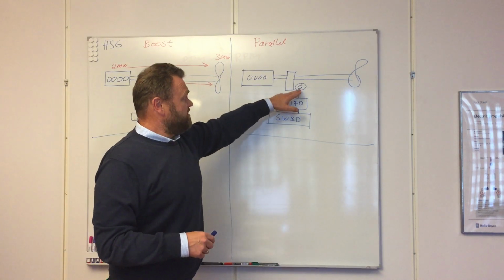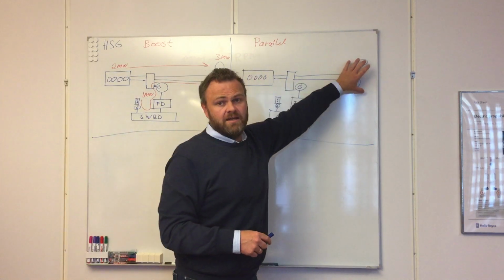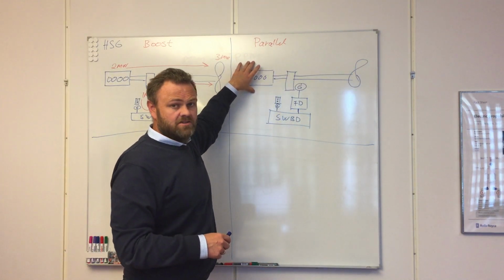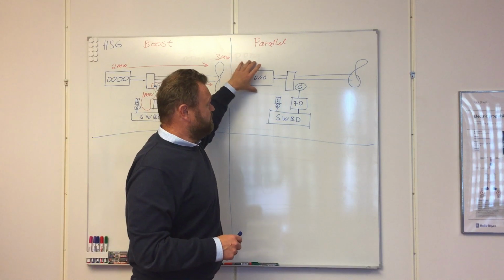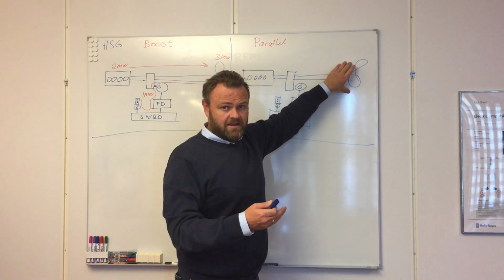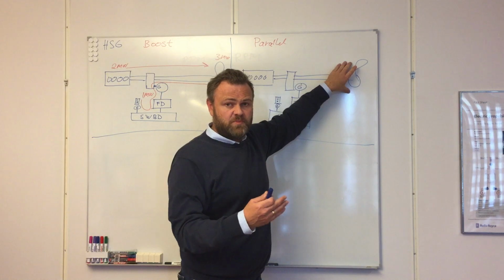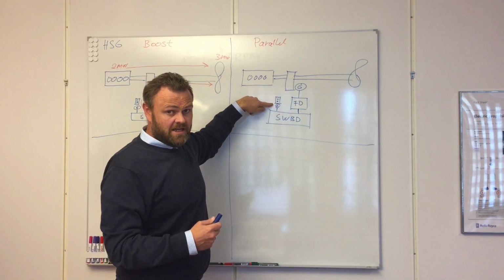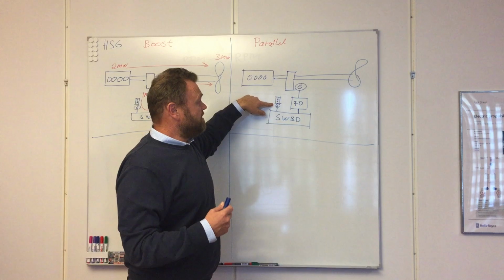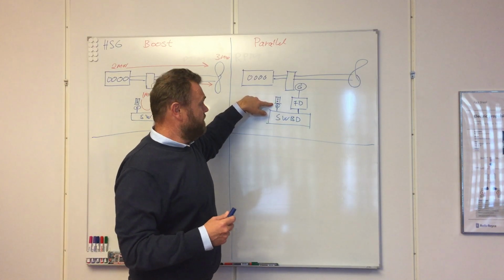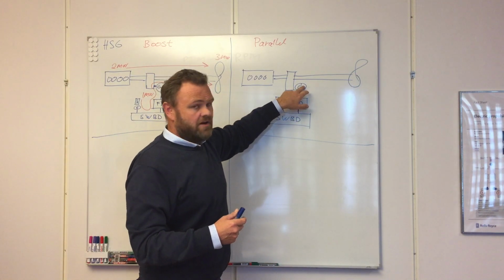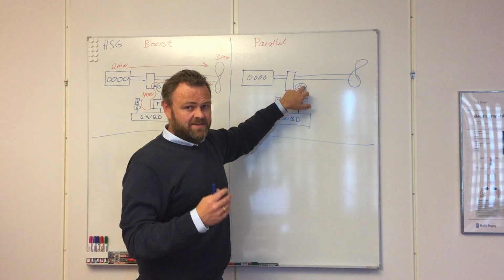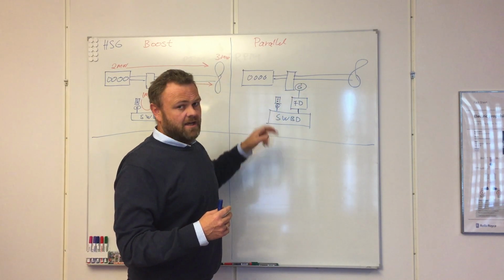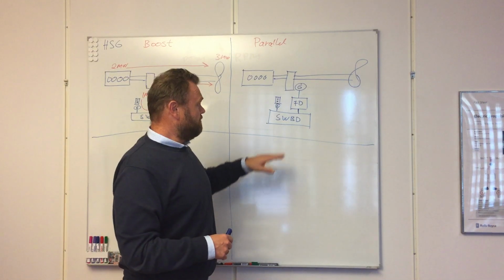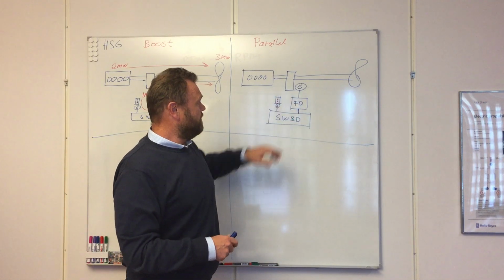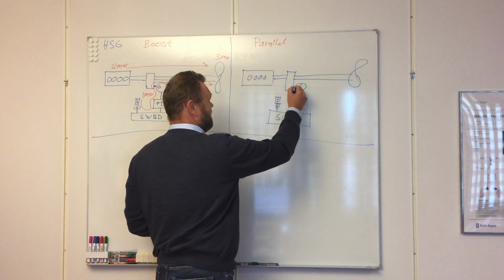And due to the fact that this generator is connected to a big mechanical system that is a bit different in the regulation response than this auxiliary engine, it is almost impossible to keep this generator frequency as stable as this one, and then you will have trouble, disconnection of one of these if you run them in parallel.